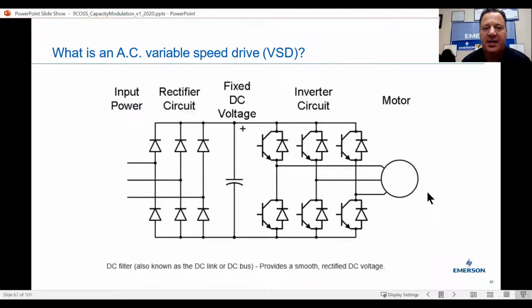Here is what an AC variable speed drive, VSD, is. Here's what we're talking about. We're rectifying it where you've got the fixed DC voltage here, and then we've got these inverters. These are switches. We've got six of them here. These insulated gate bipolar transistors, IGBTs. We're opening and closing these. So if we had real DC voltage, we would be going in one direction, direct current, right? Well, what we're doing here is we're clicking these switches on and off and making it look like alternating current. And there's different avenues this can take to this motor to work, okay? For today, all we need to know is think of them as switches, all right? They're inverters, transistors, and it's changing that frequency over and over again. We're just manipulating that frequency. So we're using the DC and tricking the motor to think it's AC.